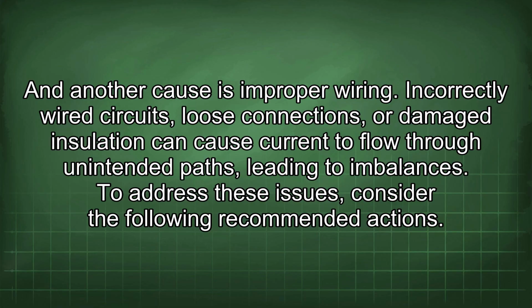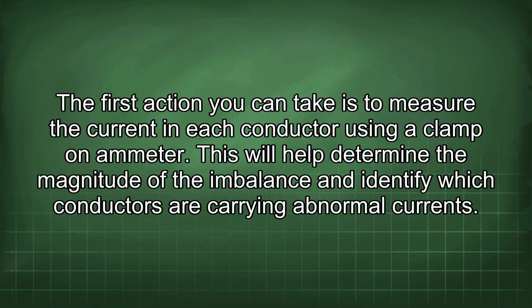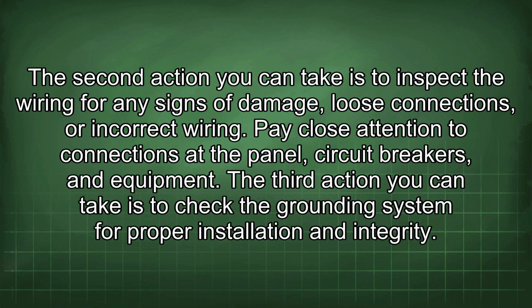To address these issues, consider the following recommended actions. The first action you can take is to measure the current in each conductor using a clamp-on ammeter. This will help determine the magnitude of the imbalance and identify which conductors are carrying abnormal currents. The second action you can take is to inspect the wiring for any signs of damage, loose connections, or incorrect wiring. Pay close attention to connections at the panel, circuit breakers, and equipment.